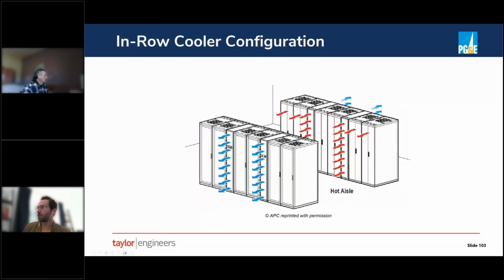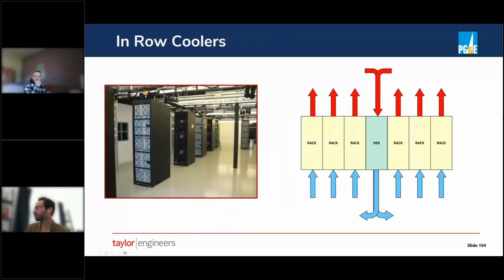Here's an example of IRC. I think Jeff actually had something very similar to this earlier. Essentially, what we're doing is taking air that's dumped into the hot aisle by the server rack and then pulling it back out with the IRC, and the IRC has a chilled water coil or a DX coil in it that then cools the air down and distributes it back into the cold aisle. And the image on the left, essentially what you're seeing is an installation where the IRCs have been plopped into the white space before the servers have been installed. In this case, we have chilled water IRCs with the valve train overhead.